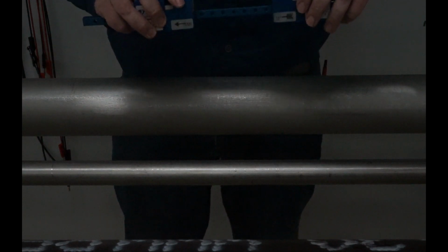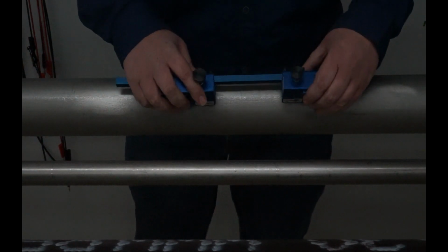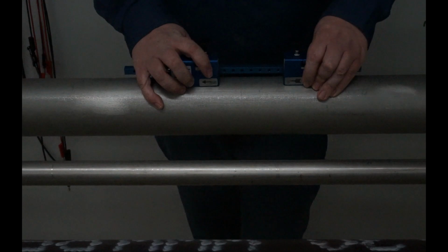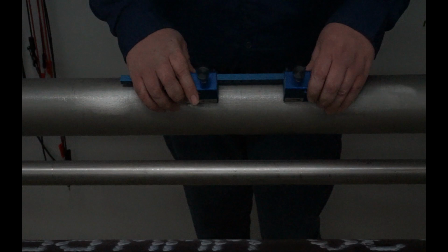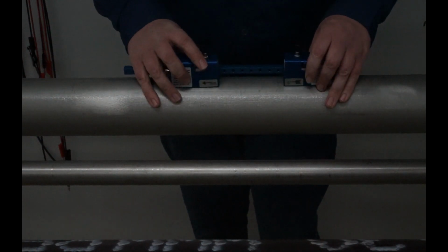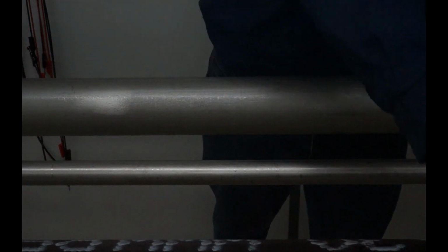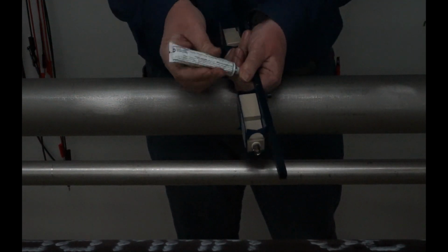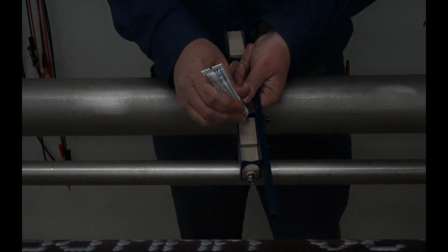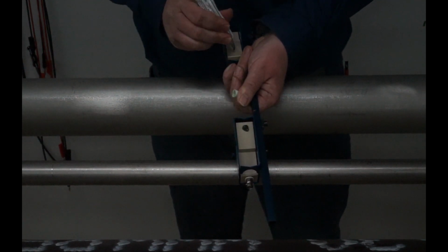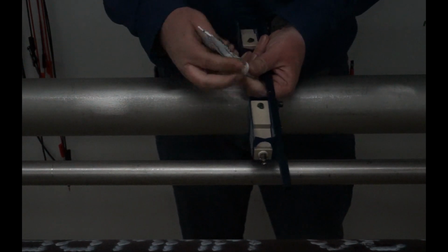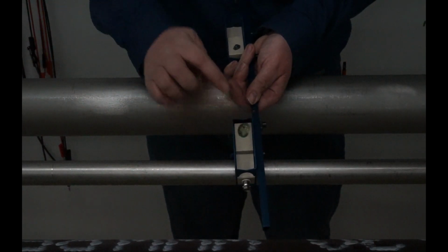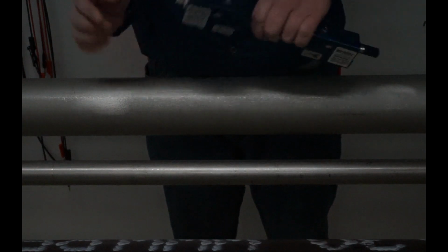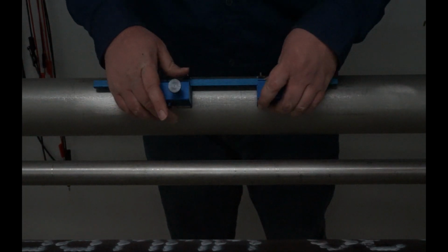When clamping the transducer assembly to a horizontal pipe, do not install it in the 12 or 6 o'clock position, because the measurement might be negatively impacted by air bubbles or debris which could accumulate at the top or bottom. Also, to make sure the transducer has good acoustic contact with the pipe, apply either a small amount of contact grease or acoustic coupling pads to the transducer as shown. Now make sure to hold the assembly firmly while attaching it to the pipe.